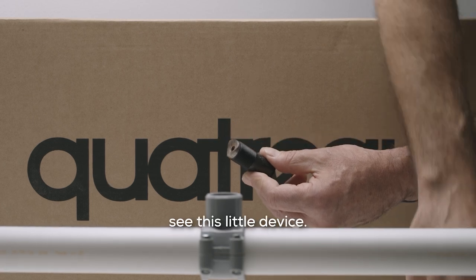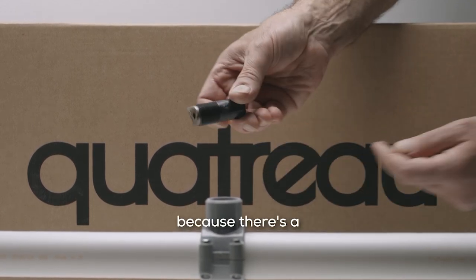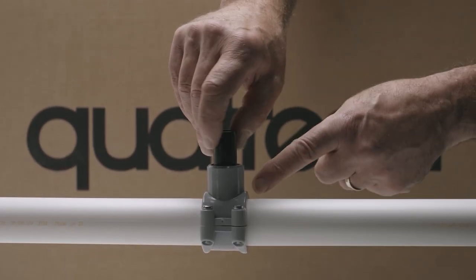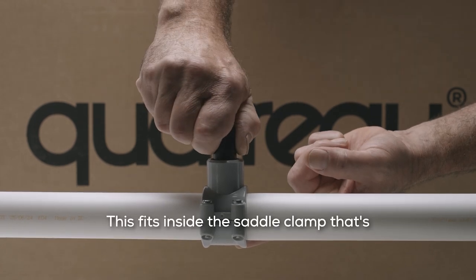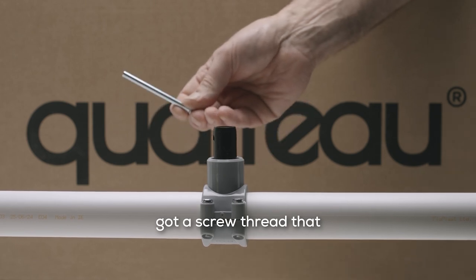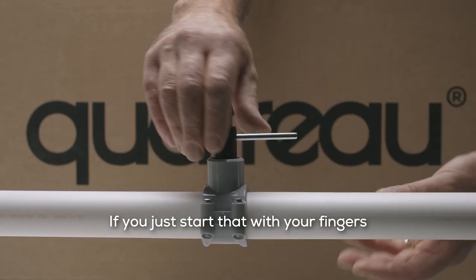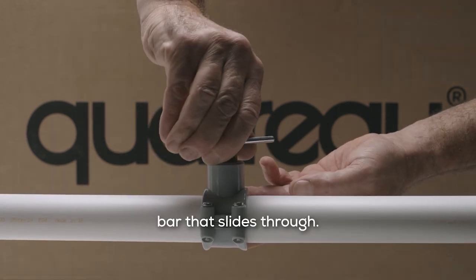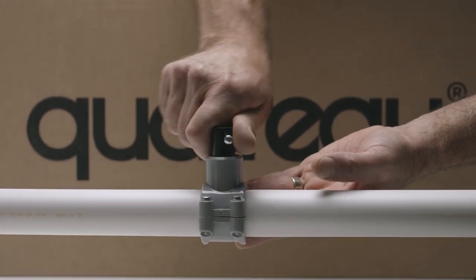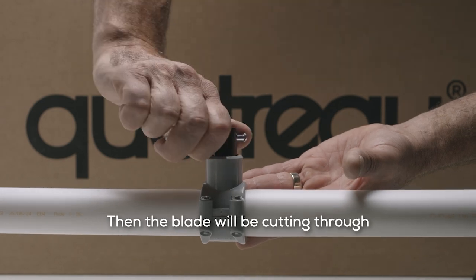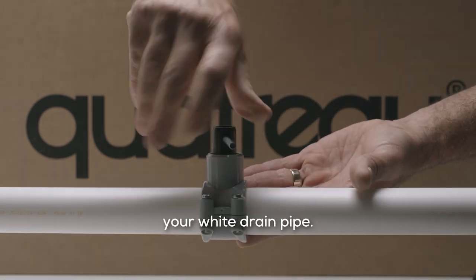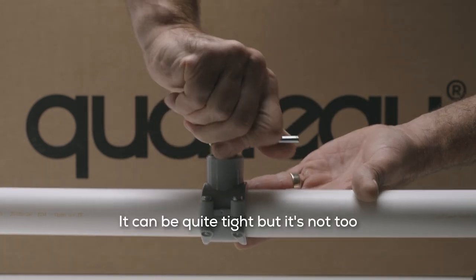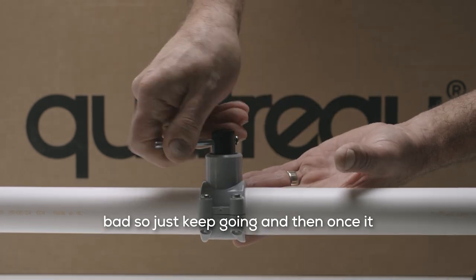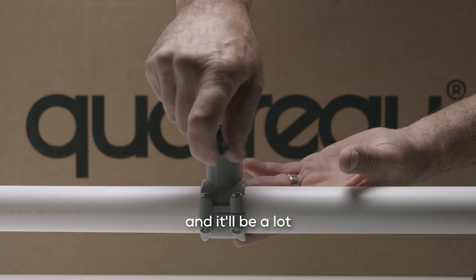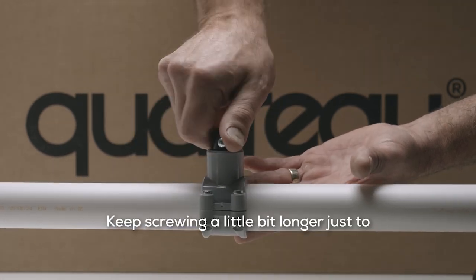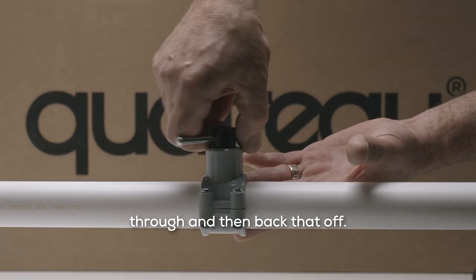And then in the kit, you'll see this little device. Just be careful when you take the cap off, because there's a sharp blade inside there. This has got a screw thread on this part. This fits inside the saddle clamp that's got a screw thread that matches the cutting device. If you just start that with your fingers, you then get a little bar that slides through. And then the blade will be cutting through your white drain pipe. It can be quite tight, but it's not too bad. So just keep going. And then once it cuts through, you'll hear a little pop, and it'll be a lot easier to turn on the thread. Keep screwing a little bit longer just to make sure that the little hole is cut through, and then back that off.